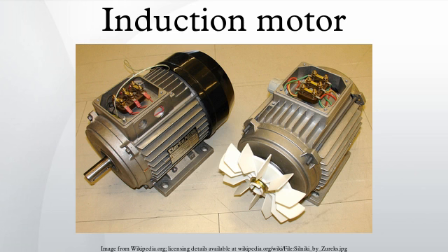Speed control. Before the development of semiconductor power electronics, it was difficult to vary the frequency, and cage induction motors were mainly used in fixed-speed applications. Applications such as electric overhead cranes use DC drives or wound rotor motors with slip rings for rotor circuit connection to variable external resistance, allowing considerable range of speed control. However, resistor losses associated with low-speed operation of WRIMs is a major cost disadvantage, especially for constant loads.